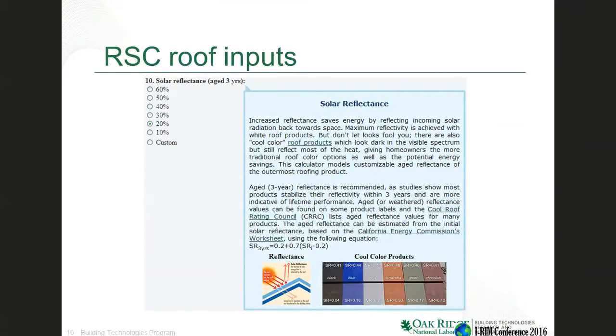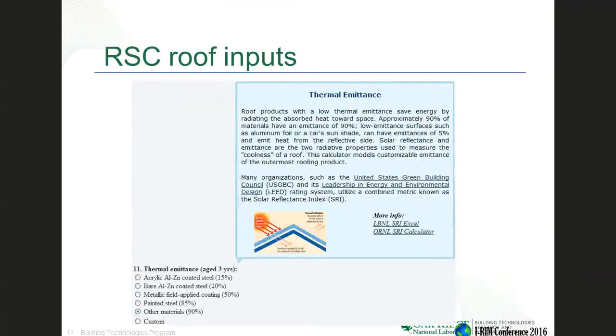Once you select a material, we have a default reflectance but you can change that. We ask that you use an aged three-year value because most products like a white roof will be very reflective at first, but in three years it drops down and hits the asymptote of where the real reflectivity of that roof is. If you don't happen to know that, you can go to the Cool Roof Rating Council — just mouse over the question mark — click that link and look up specific products to get the aged reflectance values for your material.